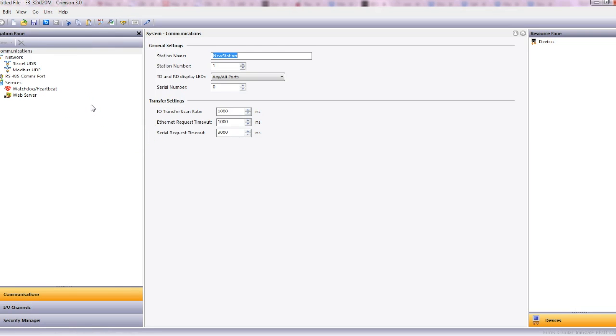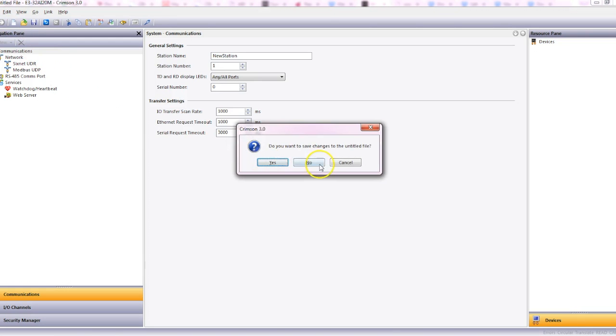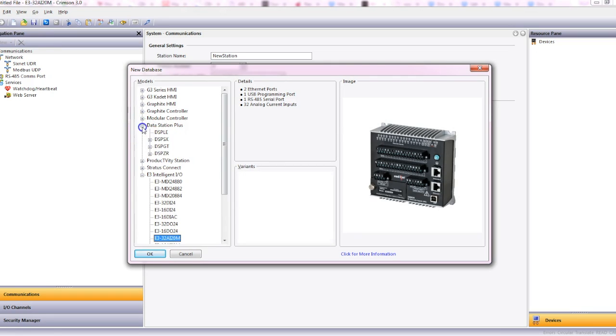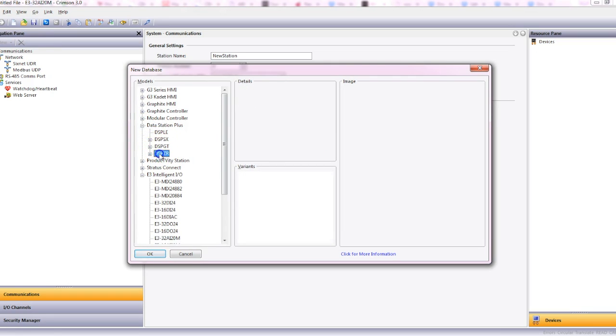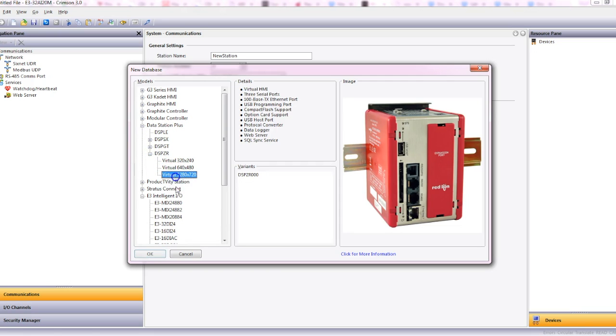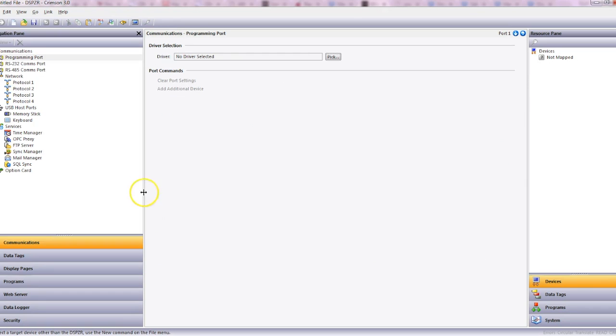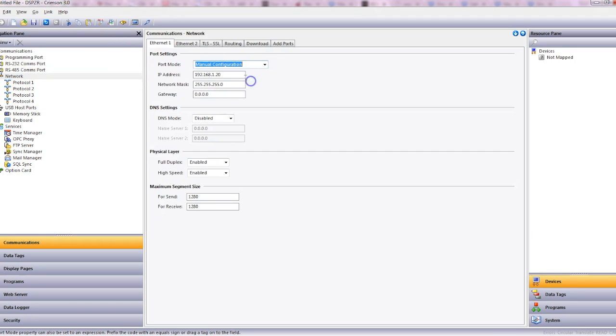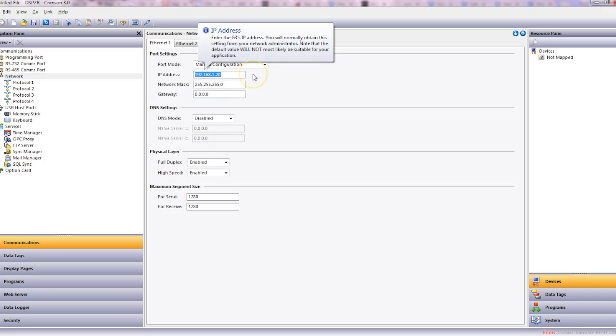Once that's in and done, we can then program the Red Lion HMI or modular controller. So let's have a look at that. Let's pick up a data station, DSP ZR for instance, which doesn't have any IO on it. So this is a great example of using some remote IO on such a device. We'll click OK. And to get that connected again, we need to make sure we're working on the same subnet. So the intelligent E3 IO was .21 whereas the data station is .20.